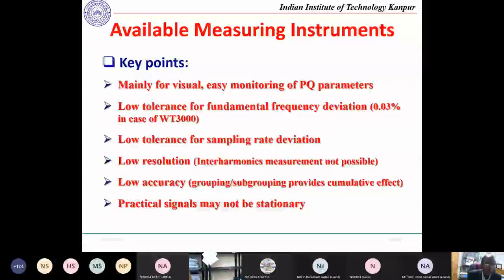They are also not able to measure interharmonics, so this is a low resolution issue, meaning they can only give the harmonic component, not the interharmonic. To understand interharmonics: suppose your frequency is 50 Hertz, so 50, 100, 150 are multiples that are harmonics. Any other frequency in between, not at 50, 100, 150, is known as an interharmonic, and these cannot be measured.